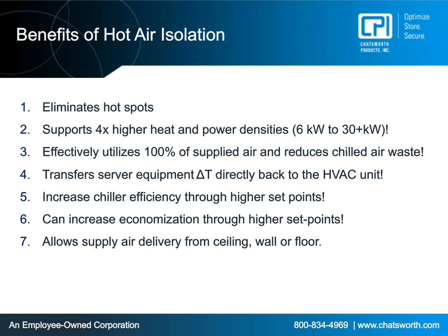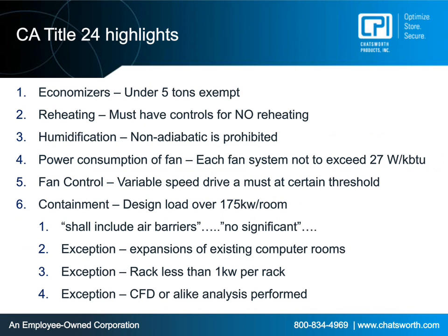So on to Title 24. Title 24 was ratified in 2013, and some of the concepts that I'm going to talk to you about today, California has now made law. So for anything under 5 tons, you don't need an economizer. You don't need to take care of outside cooling. One of my previous slides, you don't need to do that. That's a pretty low load.